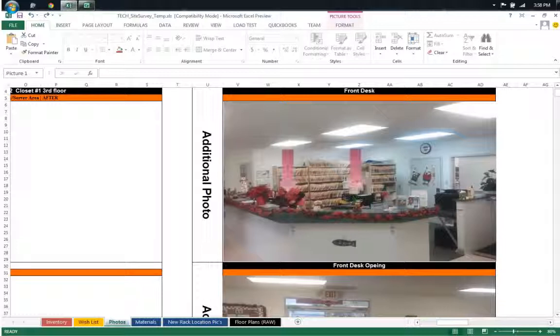There's a couple of desktops over here. We need to see where the wiring is coming in here. So is the wiring going under the ground? Is the wiring just coming over and going down the drop and then coming inside this? Or is it just mounted on that back wall? Those are the things that we can't see, but we must know in order to actually order the proper material and make sure we'll be able to support them long term.